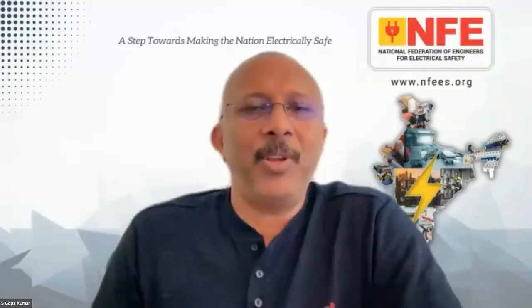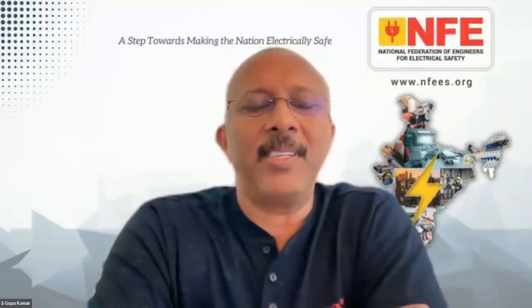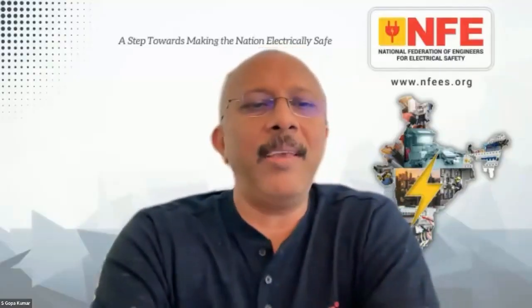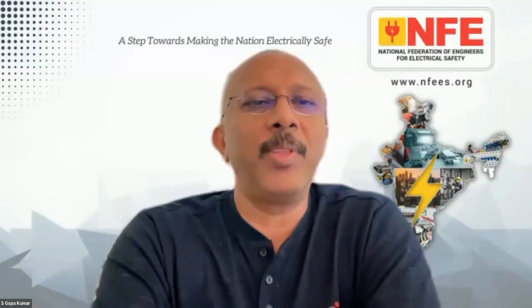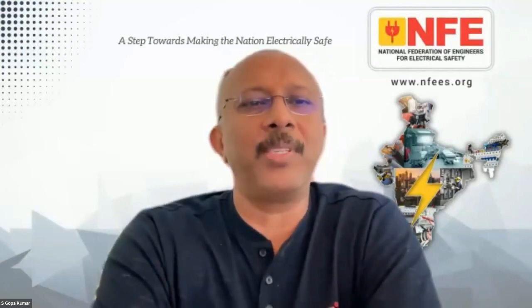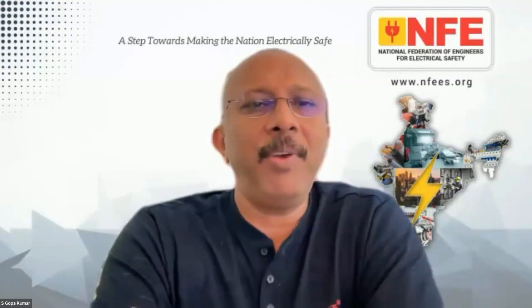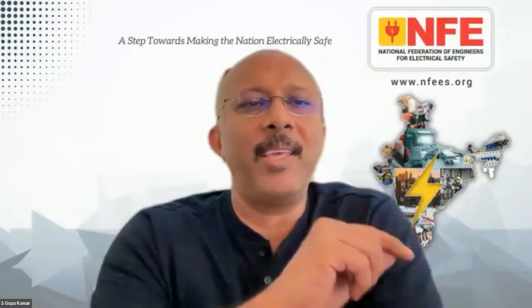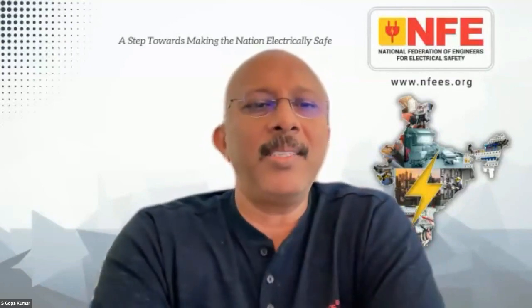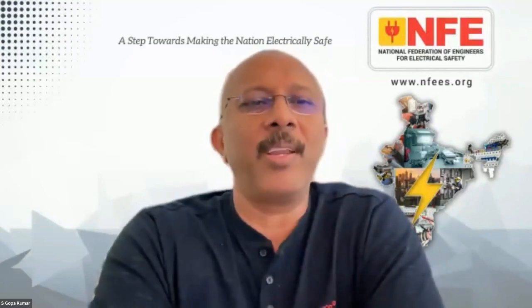Yeah. Actually, what happened is some of the equipment manufacturers, in the Indian manuals, modify it and remove the equipotential bonding part and put this separate earth electrode, because everywhere people have the impression that the symbol 5019, the earthing symbol, means a separate connection to an electrode in soil. No, that can be for a CPC, a circuit protective conductor. I don't think I would put an earth electrode for every single piece of equipment. I couldn't guarantee the safety or the performance of the equipment.